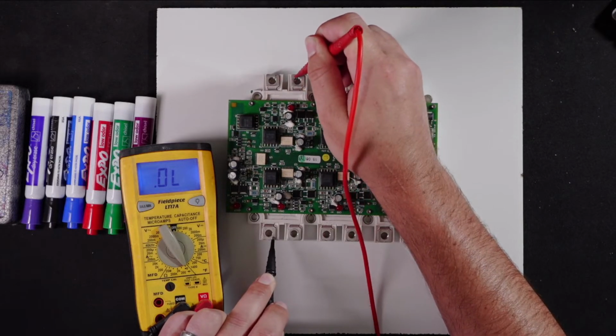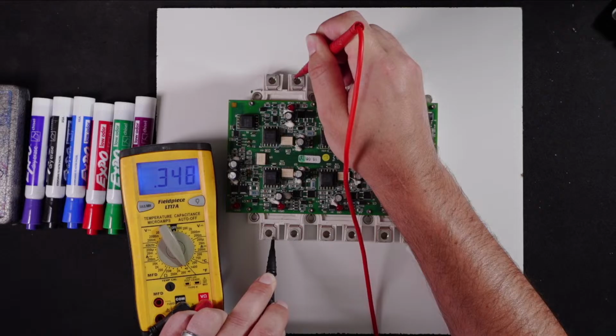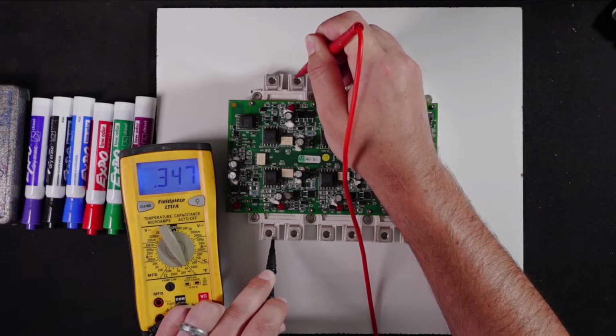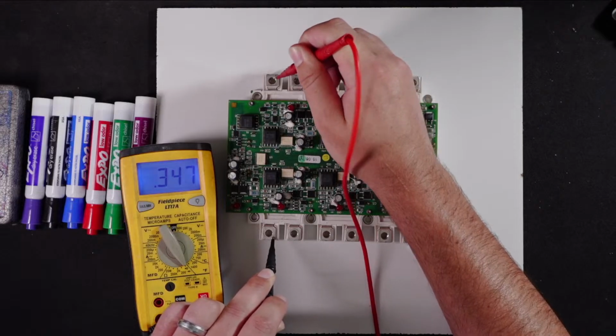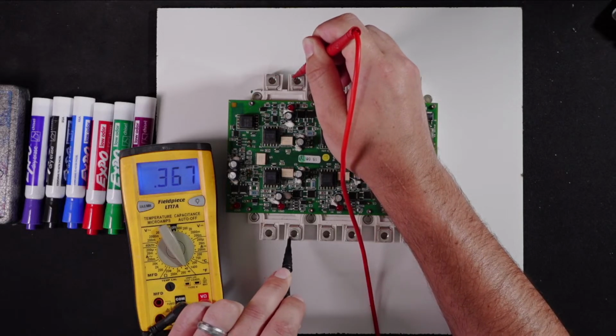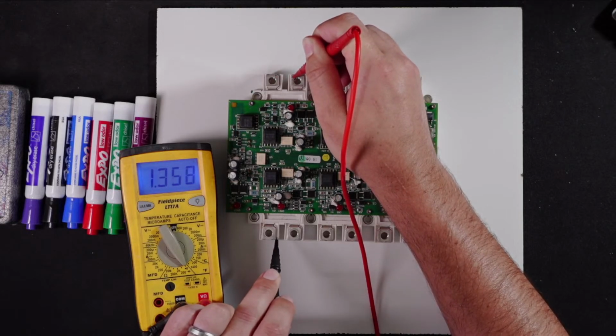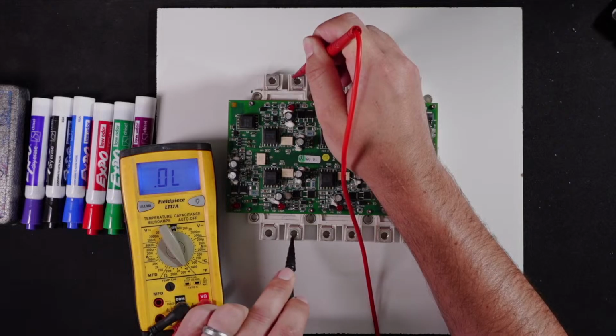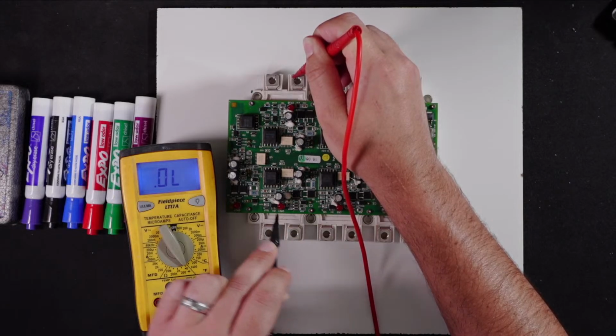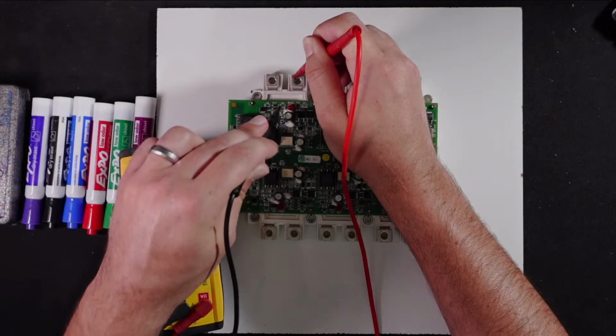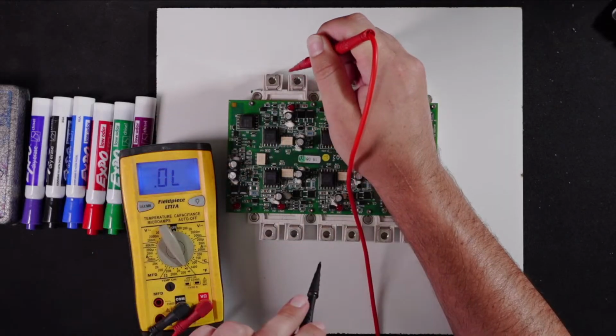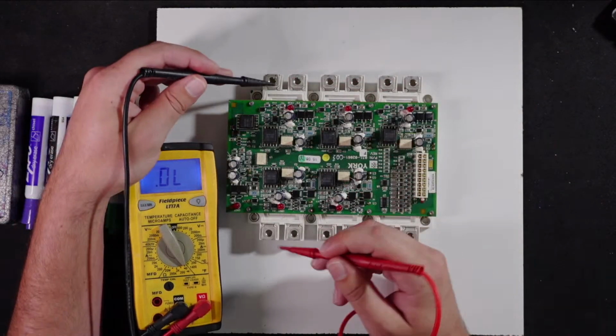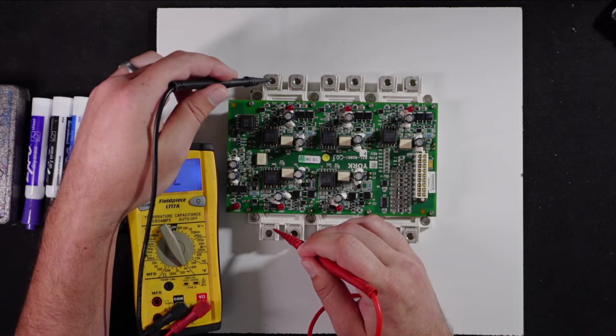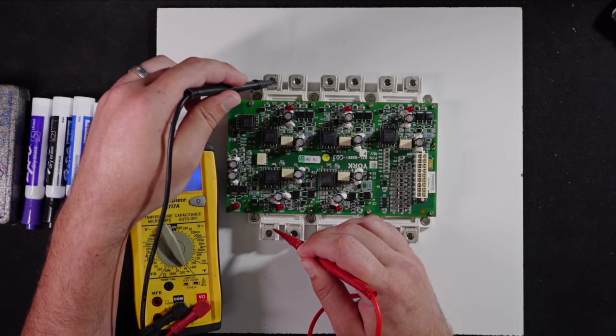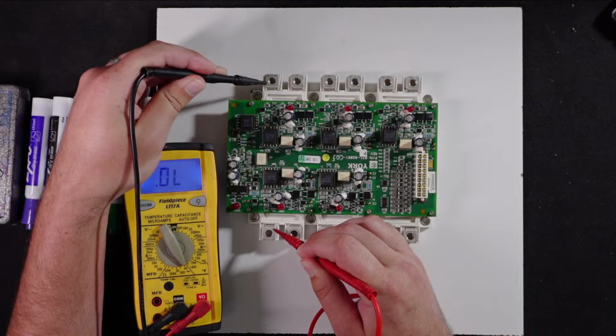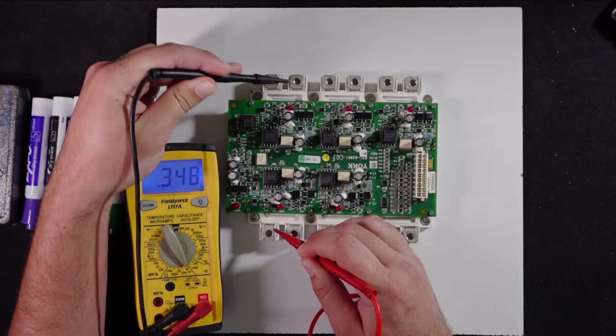We see OL, we see a 0.34. Now for this particular one, that's a good reading, and that's what I would expect to see. It doesn't matter which of these other pads I go to, I get the same thing. That's because both of these are the same output internally, and then these are two separate inputs feeding off of the DC bus. That is how we're able to create the AC sine wave, by manipulating this positive and negative DC input. Anyway, we flip the leads around, and now we're getting different readings.